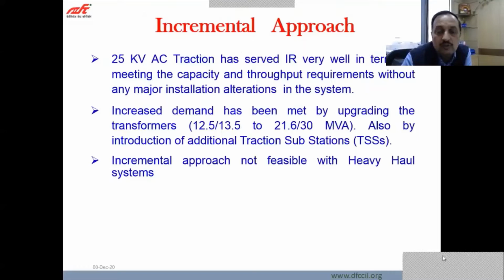So our main topic of discussion today is electrification. Indian Railways is using so far only 25 kV AC traction, and it has been performing well in terms of requirement and capacity of Indian Railways. Whenever there was an increase in demand, it has been met by slowly upgrading the transformers, like from 12.5 MVA to 21.6 or up to 30 MVA, or in case demand was more, we have introduced some additional traction substations. So this is basically an incremental approach adopted for slowly increasing the capacity.